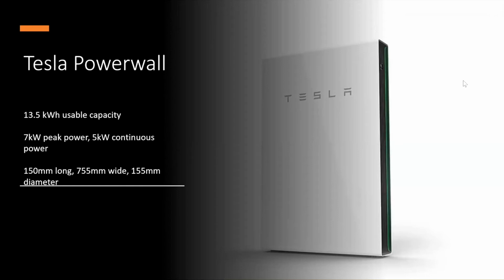It's also good to know that the location of these batteries needs to be in an area that doesn't get below freezing, so we can't put them in an unheated garage. The best place for a battery is the basement. Most people's basements, a poured concrete foundation, typically maintain about a 50-degree temperature in the wintertime, especially if you have a residual heat source down there such as a boiler or furnace. So that's the optimal place for this battery.